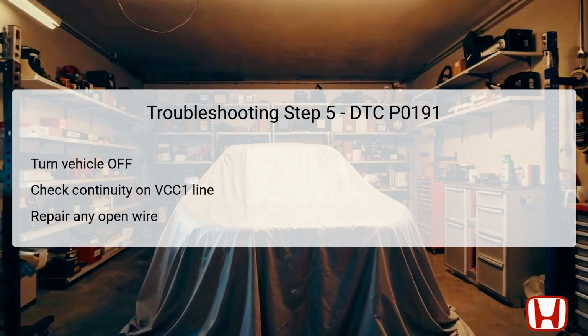If continuity is confirmed between these 2 points, it indicates that the VCC1 wire is intact and that the failure still exists within the system. In the case where continuity is not found, this indicates a fault characterized by an open wire along the VCC1 line, and repair at this point becomes necessary.